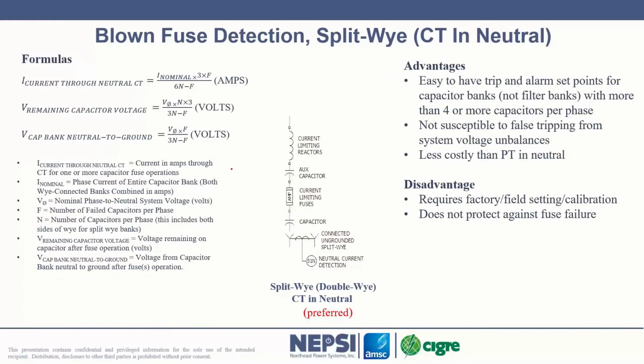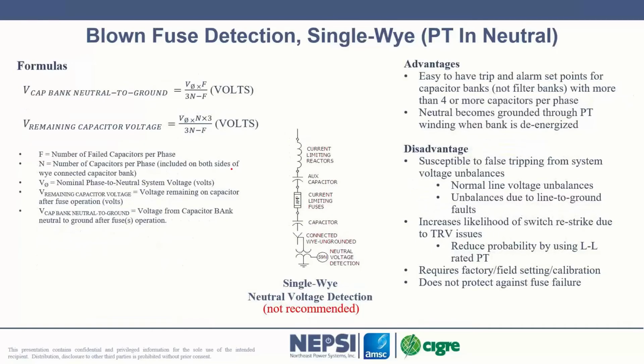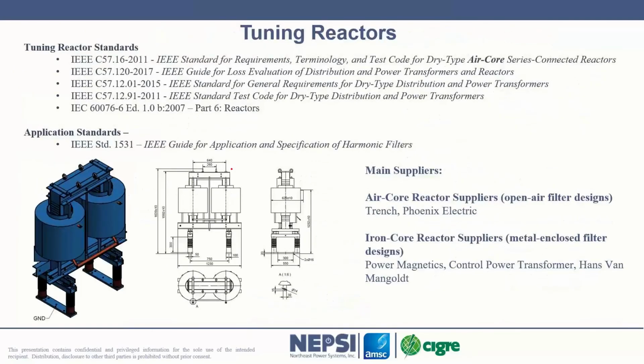The formulas are simple. Again, we have a spreadsheet tool on our website for making the calculations for that neutral unbalance scheme. For the iron core reactors or air core reactors, here I'm showing the iron core reactors, the standards that apply, and again, IEC and IEEE standards are shown here. There's really not a standard that applies to harmonic filter reactors. These are the ones that are closest to the standards utilized in harmonic filters. What we're showing here is a single phase iron core reactor.